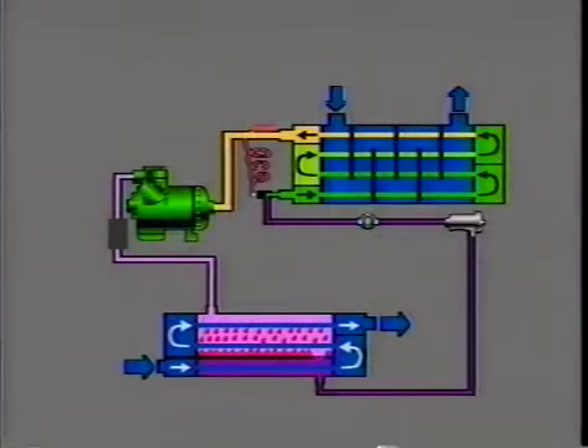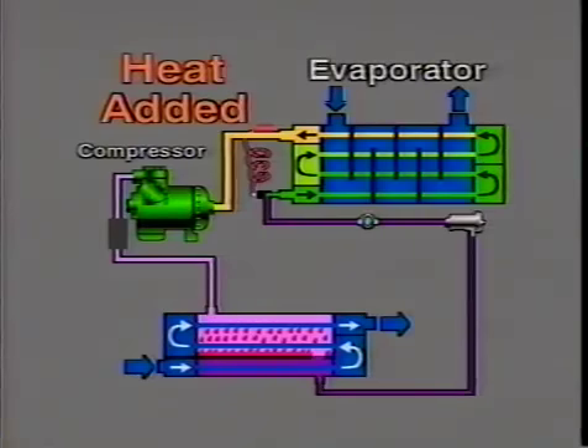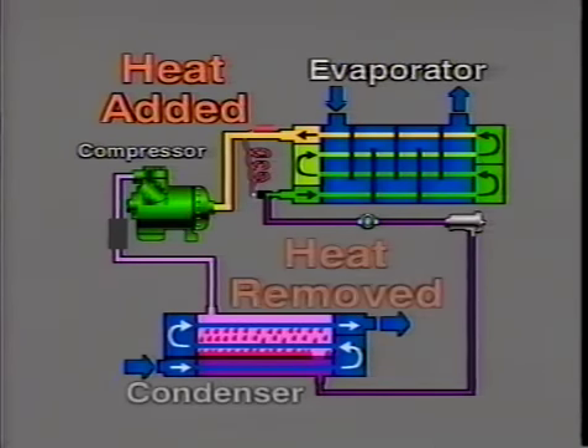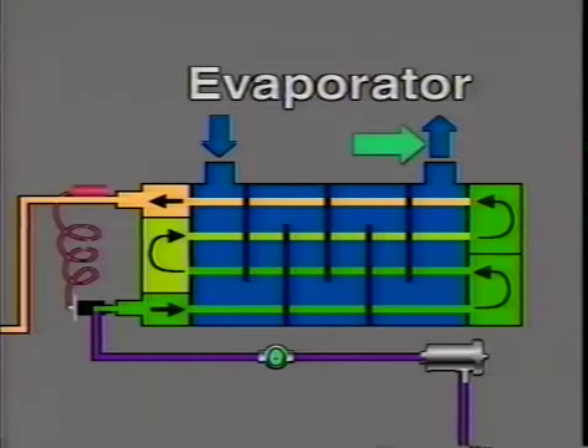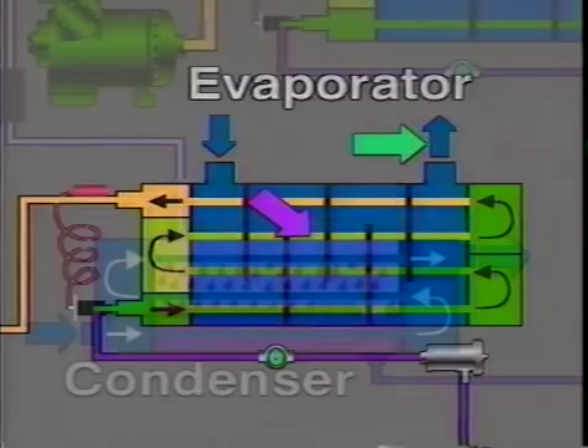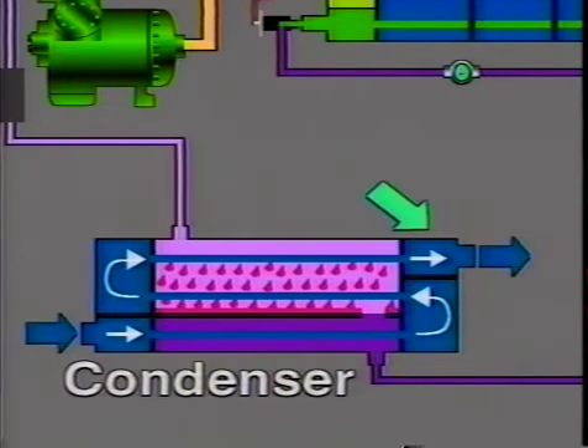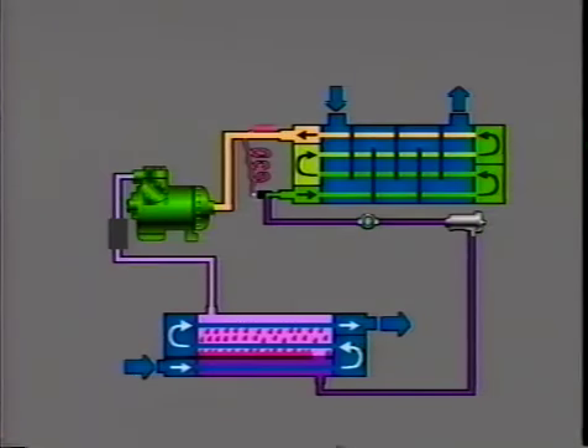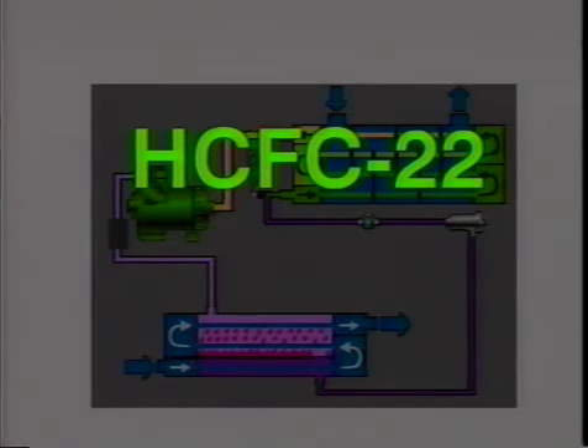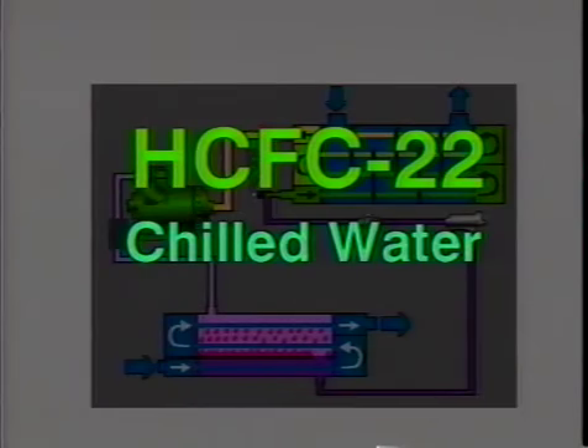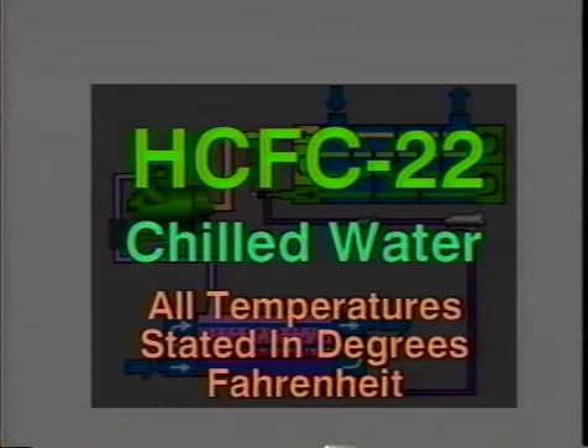As in all reciprocating refrigeration cycles, heat is added to the refrigerant in the evaporator and the compressor. It is then removed from the refrigerant in the condenser. There is a specific relationship between the temperature of the chilled water leaving the evaporator and the saturated refrigerant temperature. Likewise, the leaving condenser water temperature and the saturated condensing temperature of the refrigerant are also related. For this program, the primary refrigerant will be HCFC-22, and the secondary will be chilled water. Understanding these primary and secondary refrigerant relationships can be very helpful in troubleshooting chillers. All temperatures in this program are stated in degrees Fahrenheit.